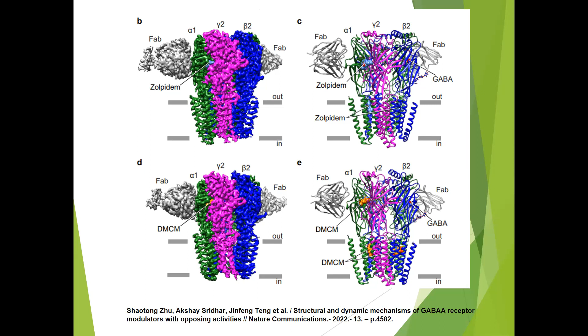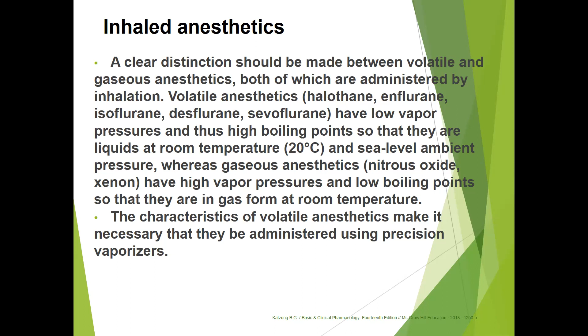Inhaled anesthetics. A clear distinction should be made between volatile and gaseous anesthetics, both of which are administered by inhalation. Volatile anesthetics, halothane, enflurane, isoflurane, desflurane, sevoflurane, have low vapor pressure and thus high boiling points, so that they are liquids at room temperature and sea level ambient pressure, whereas the gas anesthetics, nitrous oxide, xenon, have higher vapor pressures and low boiling points, so that they are in gas form at room temperature.